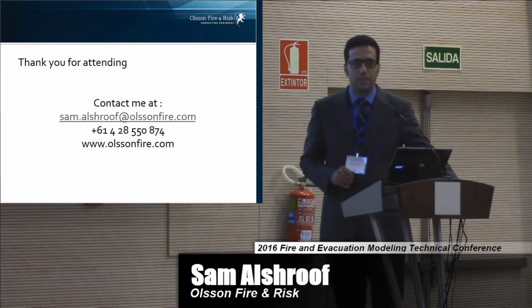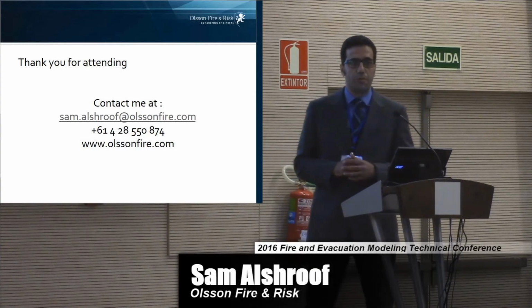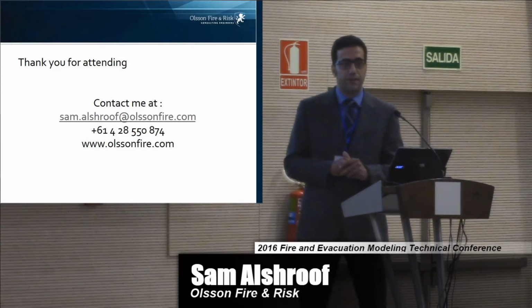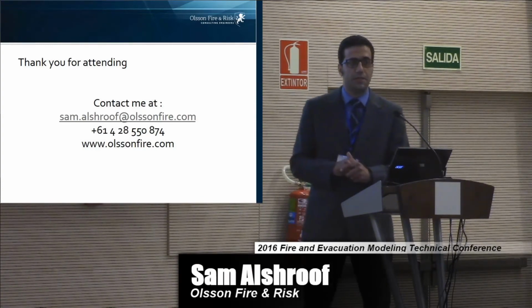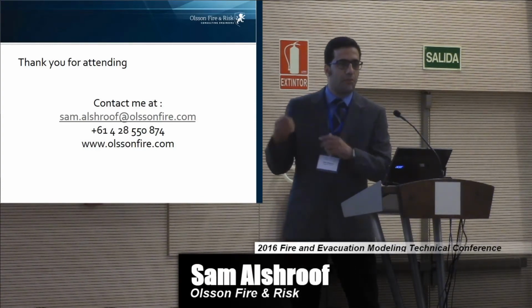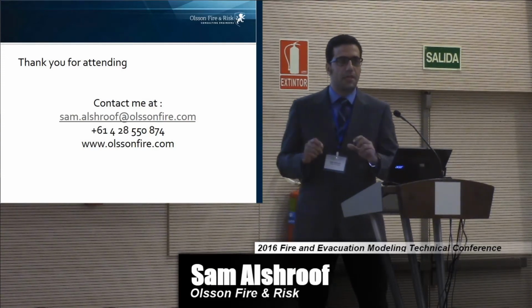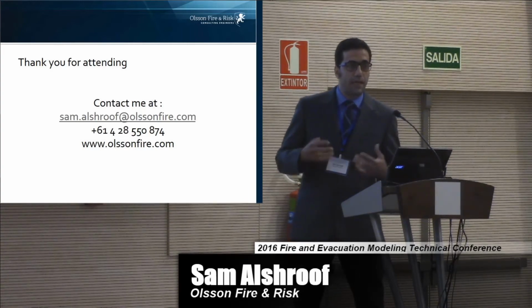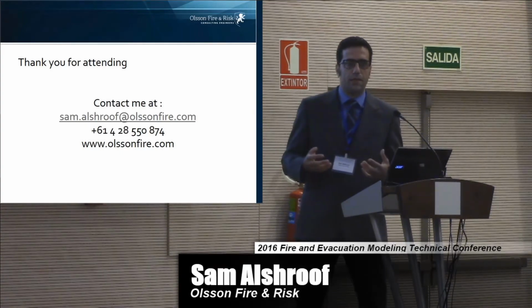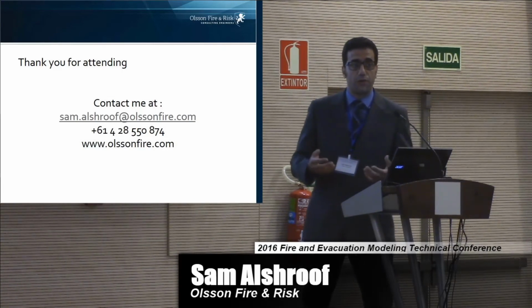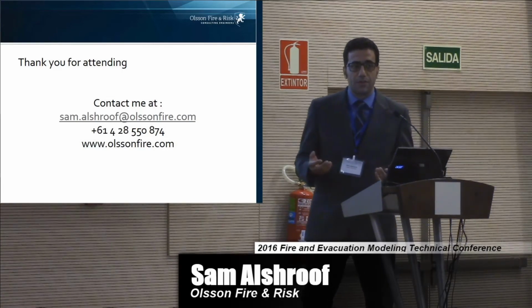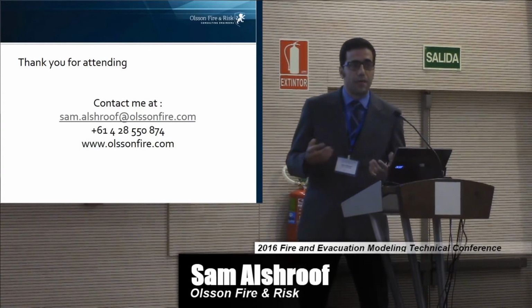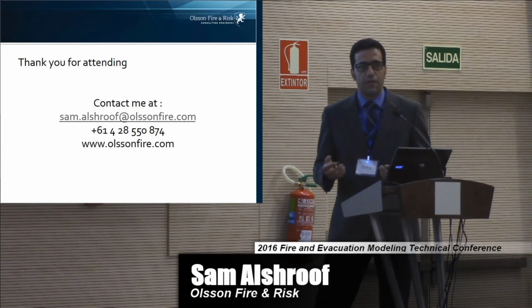I think whatever is published on the website is a very different type of problem. It's a round type JETFAN with a very large diameter. So when you compare it to these type of JETFANs where you have a nozzle 100 mil in height, how many mesh elements do you want to fit on that? To capture any inlet boundary condition in CFD knowledge, you need a minimum of 3 cells, which means that you have to have mesh in the order of 40 millimeter, and that is highly unachievable for any commercial use by the end of the day.